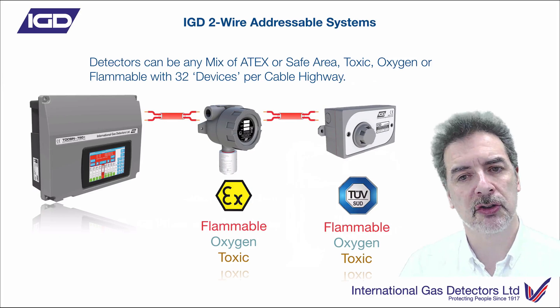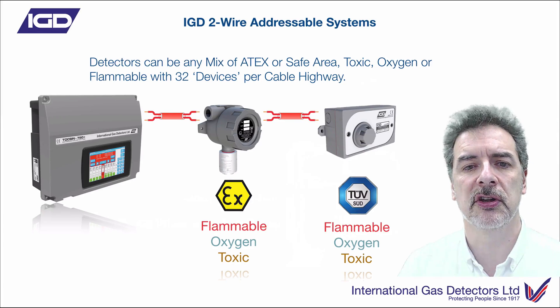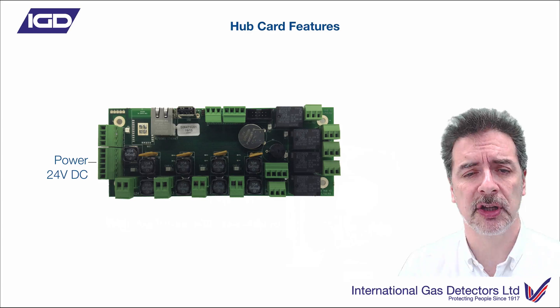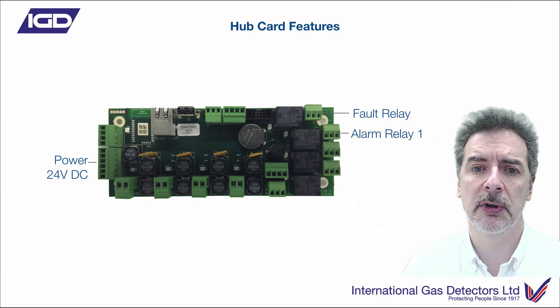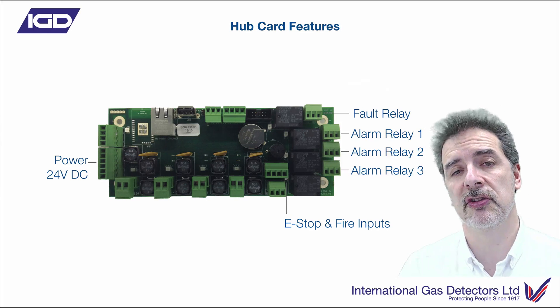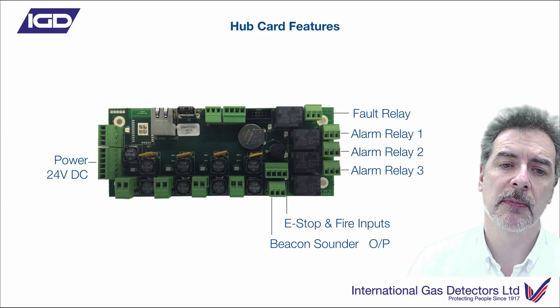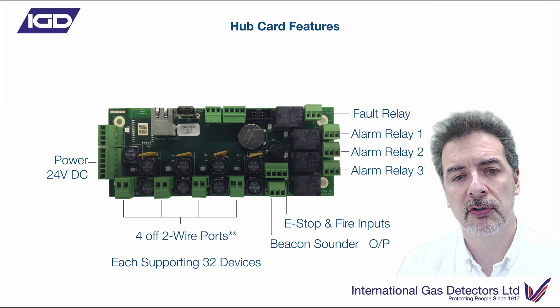Any mix of flammable, oxygen, or toxic gas detectors — either safe area units or ATEX units, whichever ones you need for the area classification you've got — and you can have up to 32 of those devices on each one of the cable highways available on the controller. The hub card itself has lots of features: there's a dedicated fault relay, three alarm relays, direct digital input for e-stops, slam switches, break glasses, or relay interfaces to fire panels and other controllers. These are closed-loop interfaces that open up to send them into alarm. You've also got a beacon sounder output there directly to control off the panel. On the 750 — the bigger touchscreen panel — you've got four of these two-wire highway ports for connecting your detectors to, and each one of those supports 32 devices.